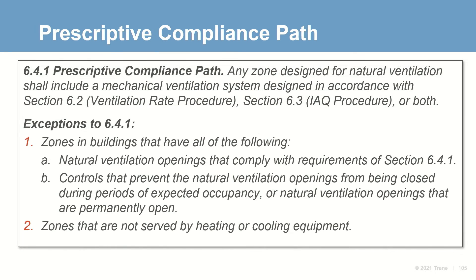The standard does include some exceptions to this mixed-mode requirement. If the openings are permanently open or equipped with controls that prevent them from being closed during periods of expected occupancy, then no mechanical ventilation system is required. Or, if the zone is unconditioned, it's also exempt.